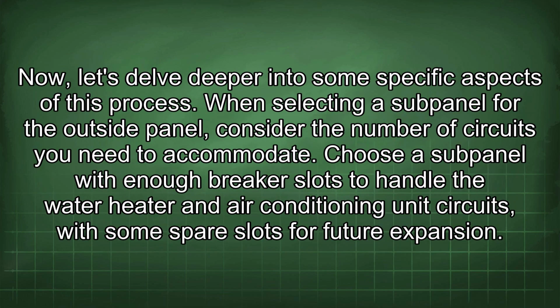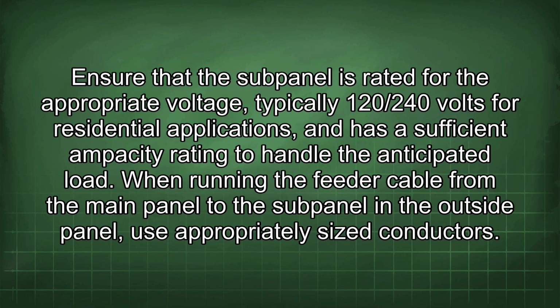Now let's delve deeper into some specific aspects of this process. When selecting a subpanel for the outside panel, consider the number of circuits you need to accommodate. Choose a subpanel with enough breaker slots to handle the water heater and air conditioning unit circuits, with some spare slots for future expansion. Ensure that the subpanel is rated for the appropriate voltage, typically 120/240 volts for residential applications, and has a sufficient ampacity rating to handle the anticipated load.